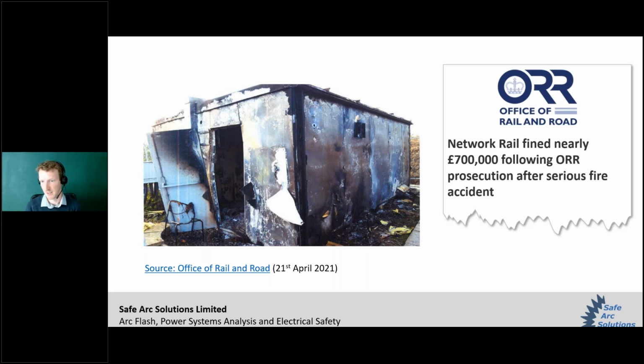Here's another fairly recent news story, involving DC equipment supporting railway electrification in the southeast of England. The arc flash occurred on a switchboard while a worker was changing out a small control fuse — a very minor task, but it led to a large fire which, as you can see from the photo, basically gutted the entire switch room. The entire switchboard had to be removed, and all the equipment had to be removed, refurbished, and refitted at a later date. This switchboard was out of action for several months after the arc flash.